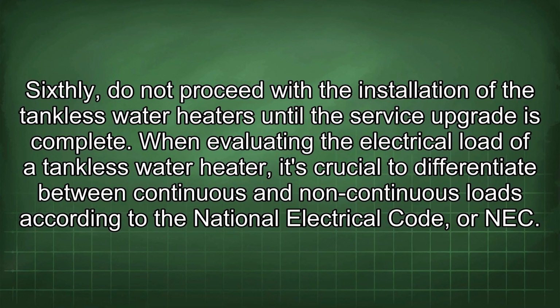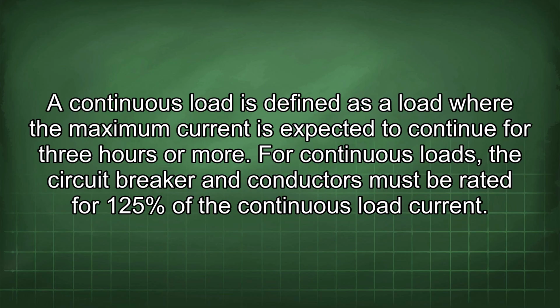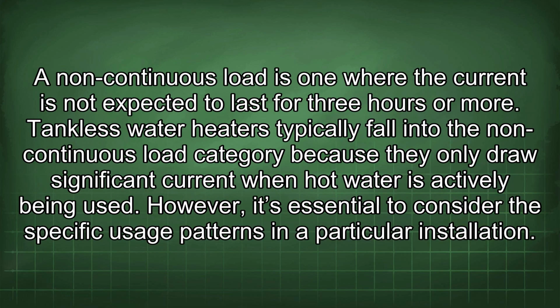When evaluating the electrical load of a tankless water heater, it's crucial to differentiate between continuous and non-continuous loads according to the National Electrical Code, or NEC. A continuous load is defined as a load where the maximum current is expected to continue for 3 hours or more. For continuous loads, the circuit breaker and conductors must be rated for 125% of the continuous load current. A non-continuous load is one where the current is not expected to last for 3 hours or more.